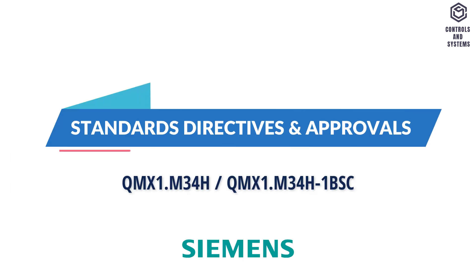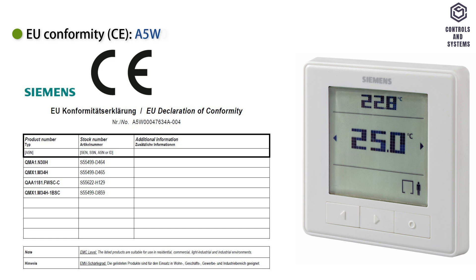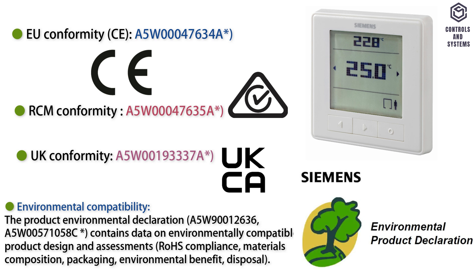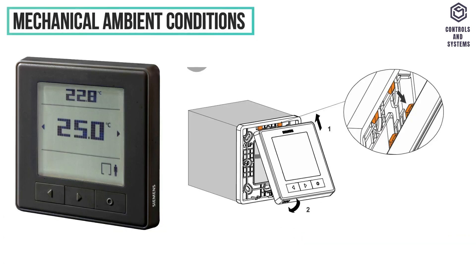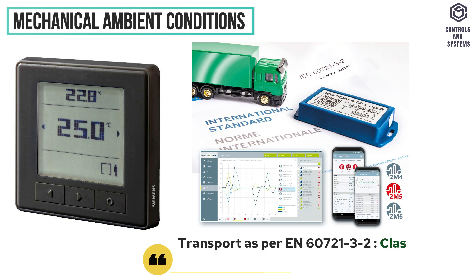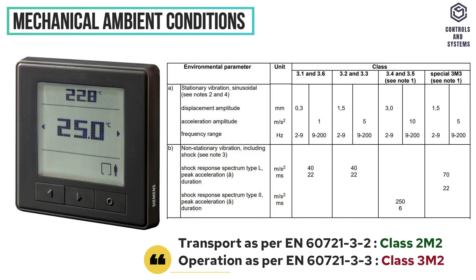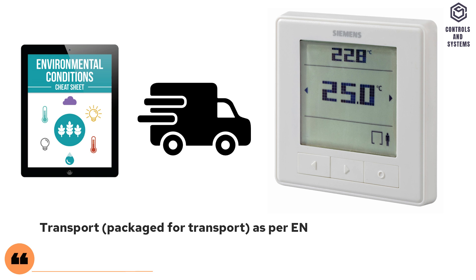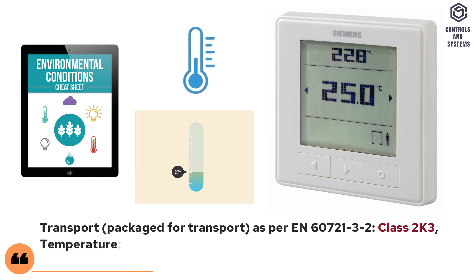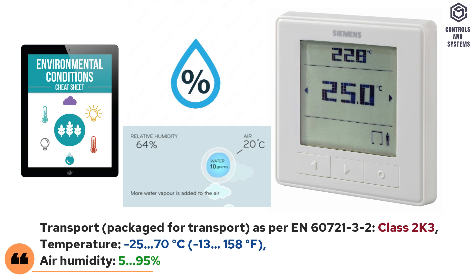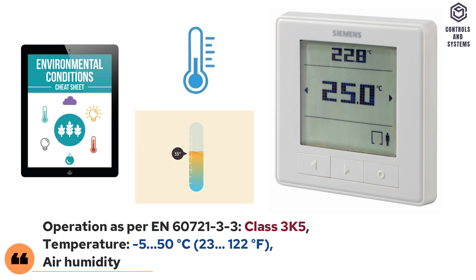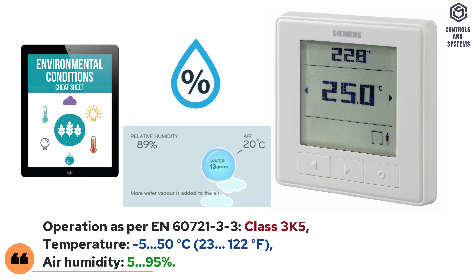Standards, directives and approvals: EU conformity CE, RCM conformity, UK conformity, environmental compatibility. Mechanical ambient conditions: transport is class 2M2, operation is class 3M2. Climatic ambient conditions: transport is class 2K3, temperature minus 25 to 70 degrees Celsius, air humidity 5 to 95 percent. Operation is class 3K5, temperature minus 5 to 50 degrees Celsius, air humidity 5 to 95 percent.